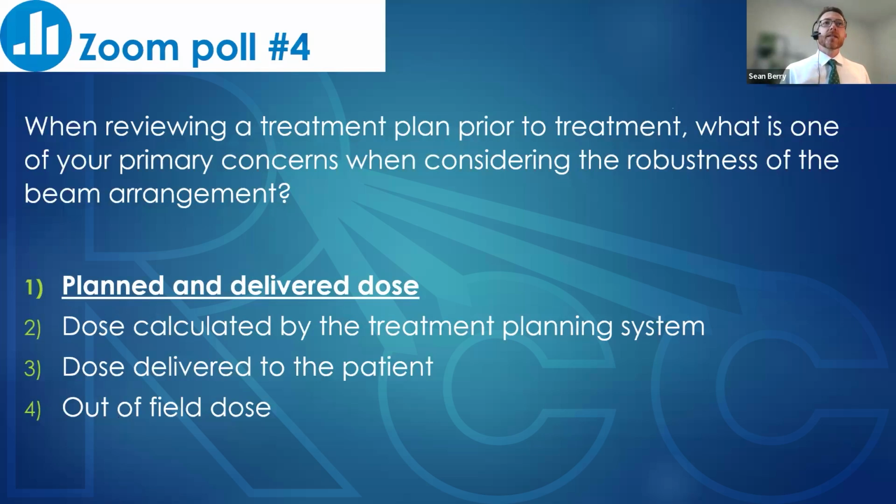Okay. When reviewing a treatment plan, primary concerns. So you are, of course, concerned about the dose calculated by the treatment planning system, but I think your focus on that part should be happening sooner, earlier in the process, kind of when you're commissioning your treatment planning system.